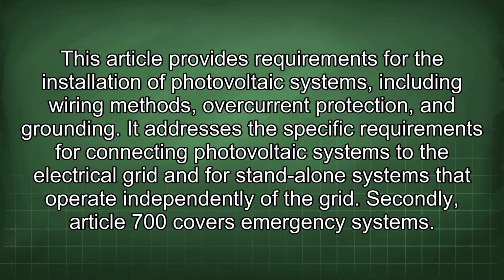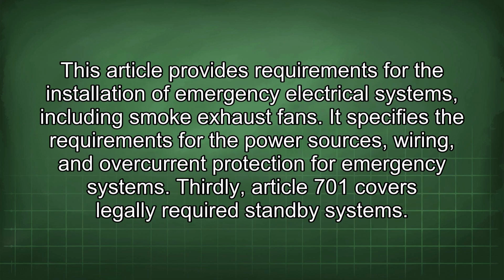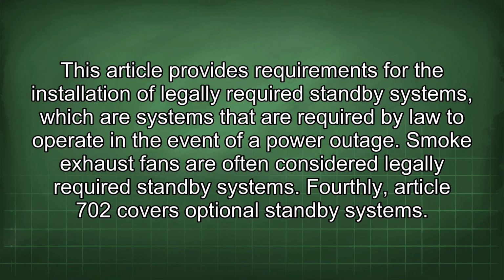of the grid. Secondly, Article 700 covers emergency systems. This article provides requirements for the installation of emergency electrical systems, including smoke exhaust fans. It specifies the requirements for the power sources, wiring, and overcurrent protection for emergency systems. Thirdly, Article 701 covers the legally required standby systems. This article provides requirements for the installation of legally required standby systems, which are systems that are required by law to operate in the event of a power outage. Smoke exhaust fans are often considered legally required standby systems.